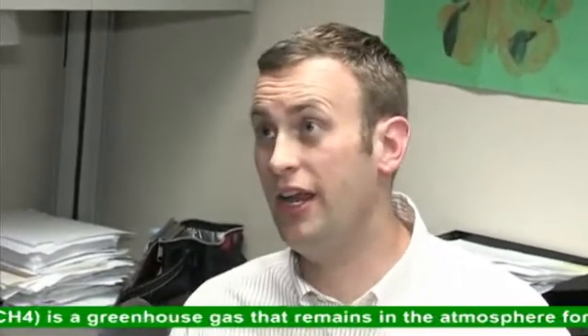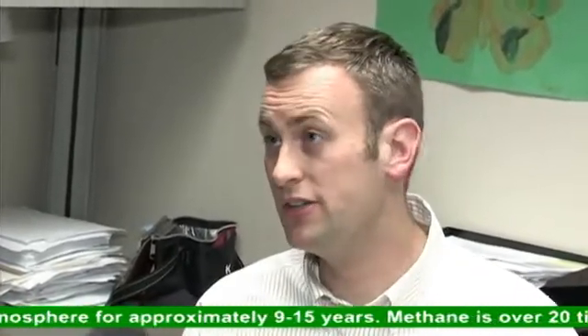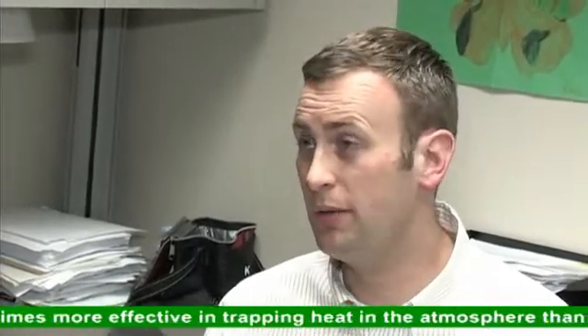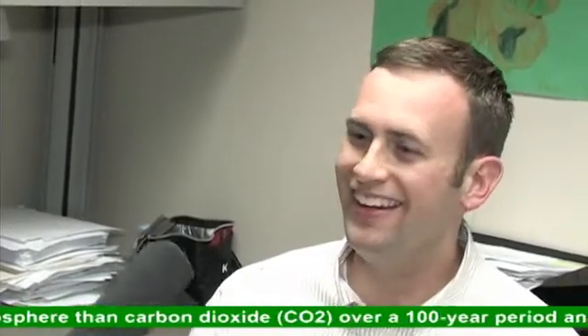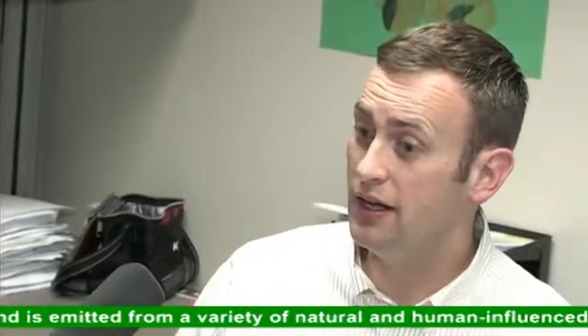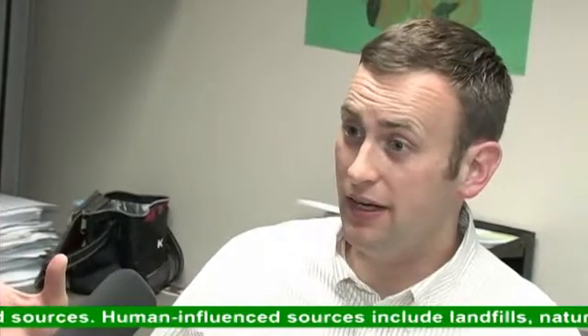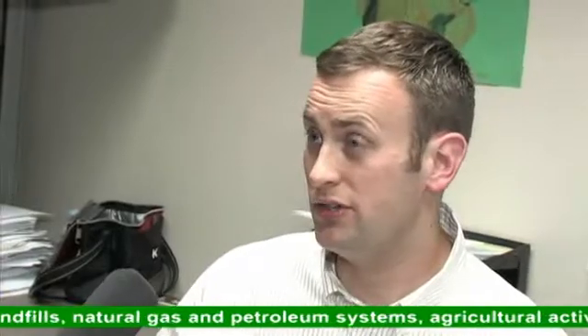Can you tell us a little bit more about the specifics of the machine? The LI-7700 is a high-speed and high-precision analyzer, so it makes very rapid, very precise measurements of concentrations. It's a self-cleaning instrument as well, so it really helps reduce the amount of maintenance that's required. The analyzer was designed for field use, so it sits out on top of the tower. It's pretty lightweight, and it's an open-path instrument, so it doesn't require quite as much infrastructure as a lot of other products.